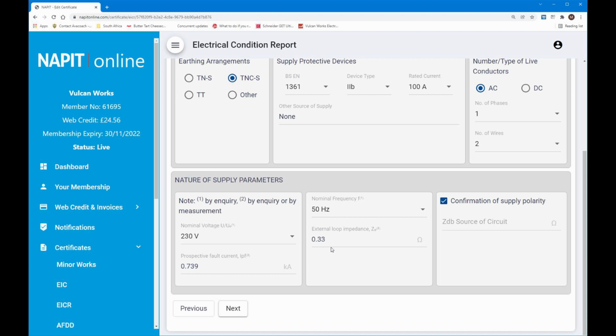So that was a bit of a faux pas on my part. So I disconnected that and redid the reading, and sure enough, 0.33. So yeah, that's the importance of making sure when you do the external loop impedance, or the Ze, make sure you haven't got any parallel paths. It does muck up the readings. So yeah, anyway, that's what it is. It's 0.33.